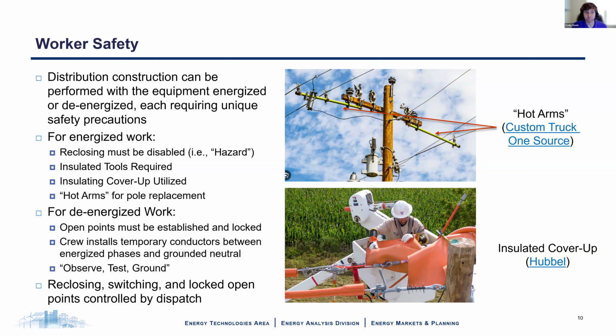When it's not feasible, when you're working on things that are de-energized, the idea is to prevent them from becoming energized by accident and to make sure that if they do, there is no risk to the people who are doing the work. So this is accomplished by establishing where your open points are that are not connected to the system and physically placing a lock on those switches. The crew also generally installs temporary conductors referred to as grounds between the energized phases and the neutral so that if it does become re-energized, it will immediately trip and fault, and all of that fault current will pass through the grounds and not through the people who are doing the work.